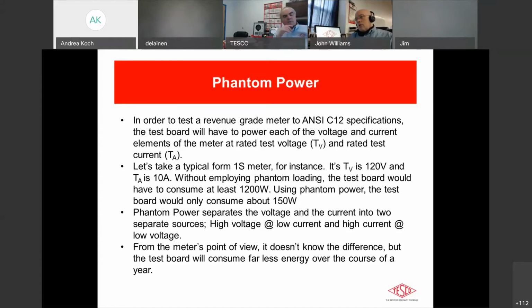Now, for the bigger utilities, you have whole walls full of test boards, or even a simple 4 or 6 position board, that adds up to a lot of energy, right? A lot of heat. Folks in the lab are going to get upset because the temperature in the room just shot up because of all the energy being put out into the atmosphere. So phantom power is very simple in its concept, a little bit harder in practically producing it, but we've of course perfected that. It separates the voltage and current into 2 different sources, 2 different power supplies, if you will.